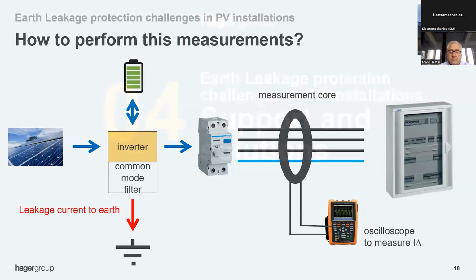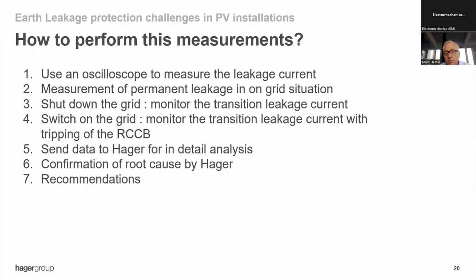What you can do is use this oscilloscope to make this measurement. You can measure the permanent leakage in on-grid situation. You can shut down the grid and see what happens during this first transition. But apparently, when the grid shuts down, there is no problem of tripping, as far as we understood. The problem occurs when the grid comes back. So you can switch on the grid and measure this transition leakage current and see if the RCCB is tripping. And this would be helpful to know about the level of the currents, also the duration of the transition. We are happy to get this data from you and to analyze it and to give you some advice to confirm the root causes and to make some recommendations.